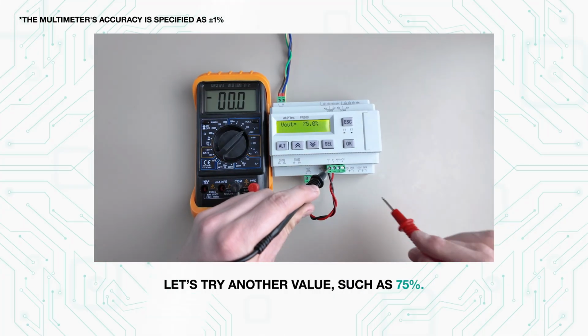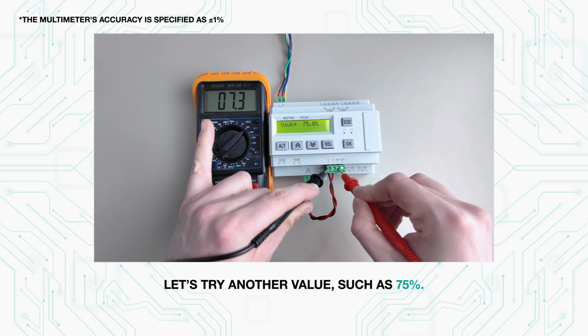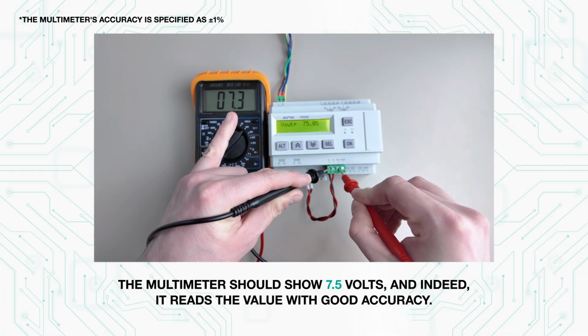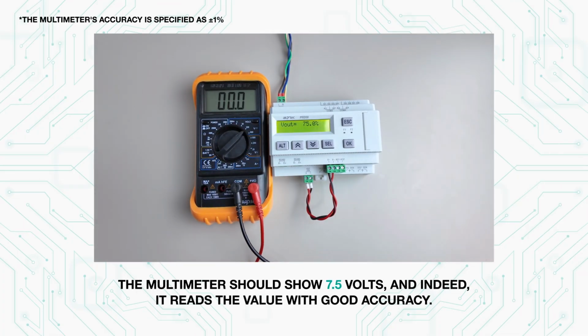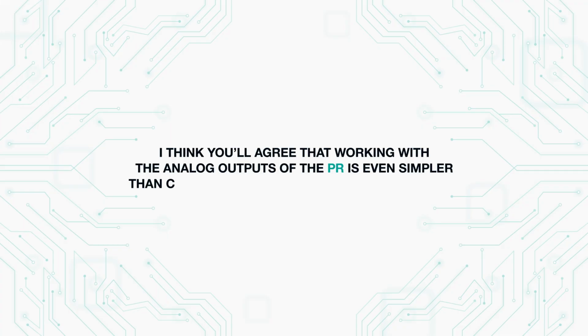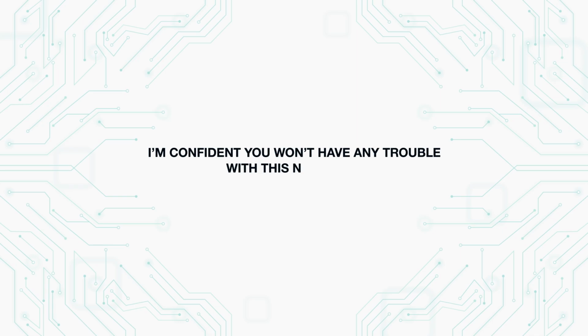Let's try another value, such as 75%. The multimeter should show 7.5 volts, and indeed it reads the value with good accuracy. I think you'll agree that working with the analog outputs of the PR is even simpler than connecting signals to the analog inputs. I'm confident you won't have any trouble with this next time.